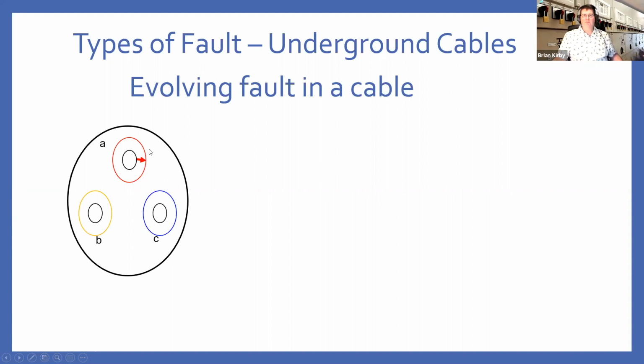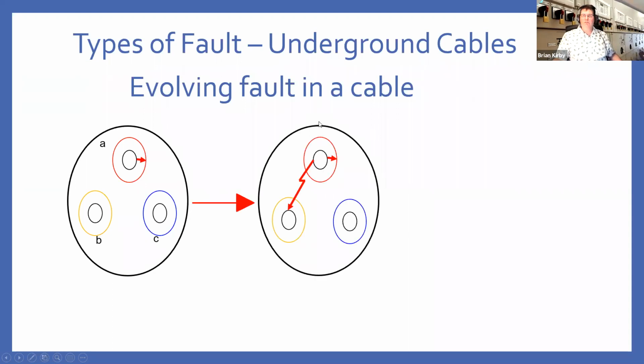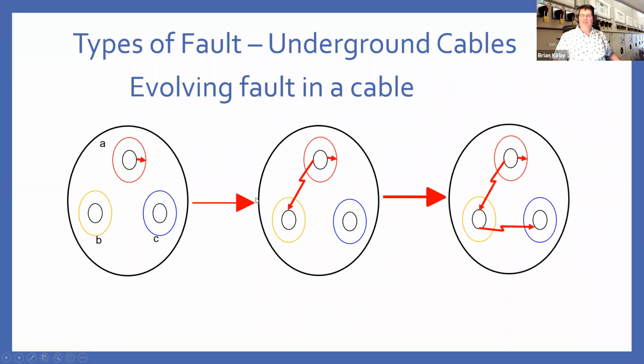And eventually, the deterioration gets sufficient that it becomes a phase-to-phase fault. And at this point, you're now starting to see rapid deterioration of the insulation because the energy levels have grown sufficiently that it can leap across. And before long, if your protection hasn't detected that, you get yourself to a three-phase fault on your cable. And the only thing you're going to see after that is a bang as the cable blows up. There are lots of YouTube videos of these things happening. I thought about putting one in, but then I decided they were all too long. But if you want to go and search underground cable explosions, you'll find loads of them on YouTube.